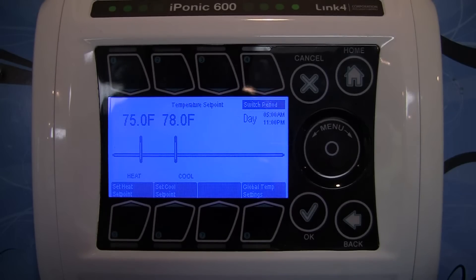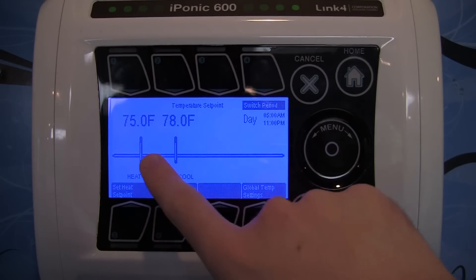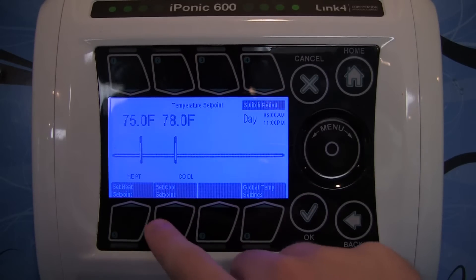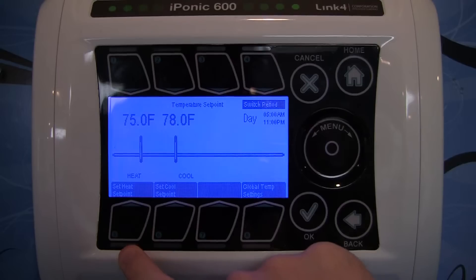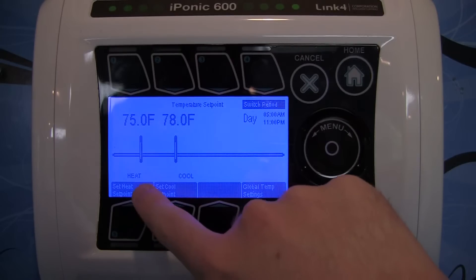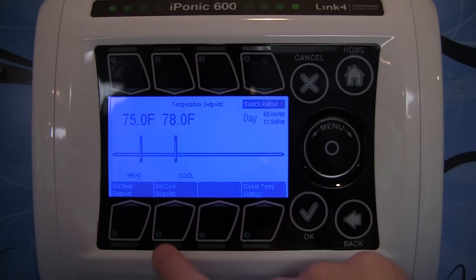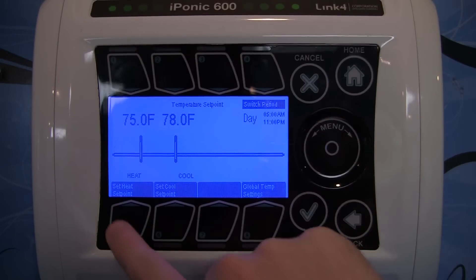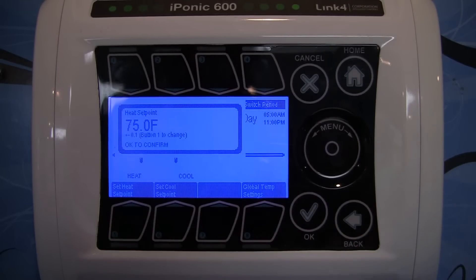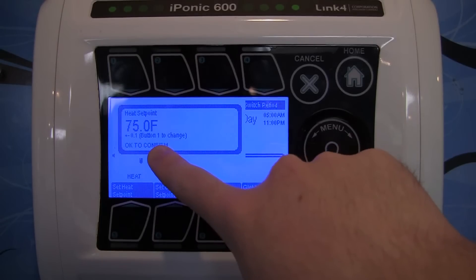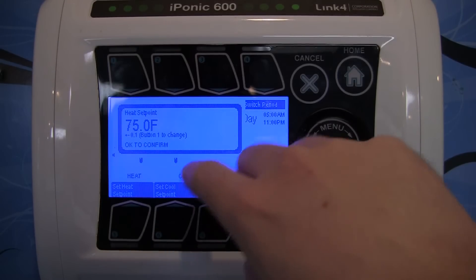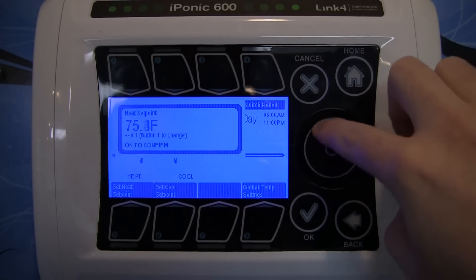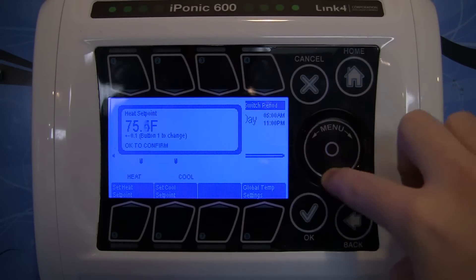The two temperatures are known as the heat set point and the cool set point. You can change them by going to the bottom of the screen — number five says set heat set point and number six is set cool set point. Selecting the heat set point brings up a menu where by default you can use the scroll wheel to move in increments of 0.1 degrees.